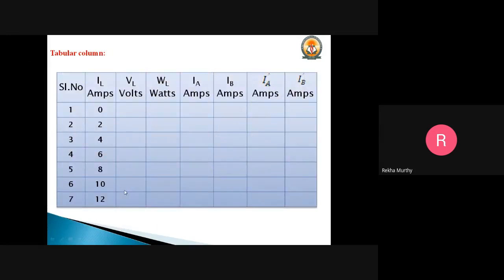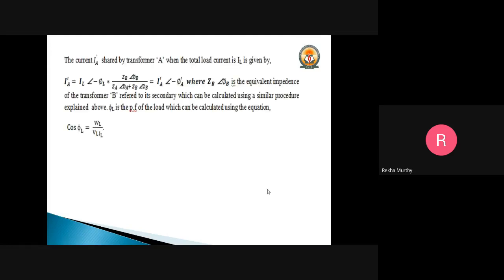So here the final table will be with the different ratings. As I told you, we are going to vary 2 amperes, then 4 amperes. This is all the variation with respect to the resistive load bank, and it should not exceed 12 amperes. And these are the respective voltage, wattmeter reading, IA, IB, and IA dash and IB dash values which will be taken. So IA dash can be calculated by using this formula, that is IL with an angle of minus phi L, multiplied by ZB at an angle of phi B divided by ZA at an angle of phi A plus ZB at an angle of phi B.